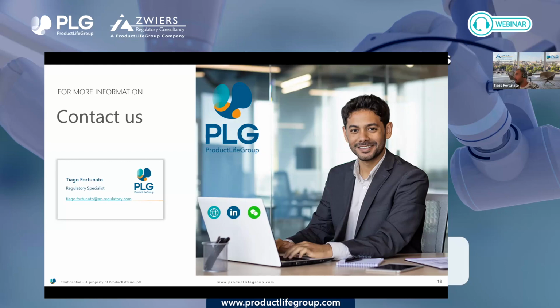One thing I'd say that's very relevant is that because you need to determine the state of the art, it is essential that you do this literature search that is required for the clinical evaluation to use it as an input. So even if you haven't done all the other steps of the clinical evaluation, the literature search is essential for this.